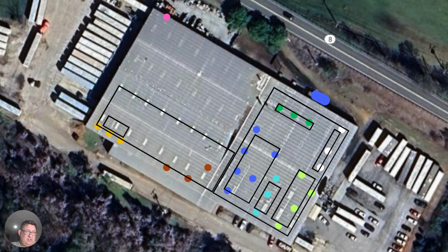We have pressure at the FRLs, right, at the processes. But remember also, we have zone pressures, and you see that here with the subloop design. You see that you have a zone level pressure control. And then also don't forget that inside your process equipment, you also have pressure control inside the process equipment itself.